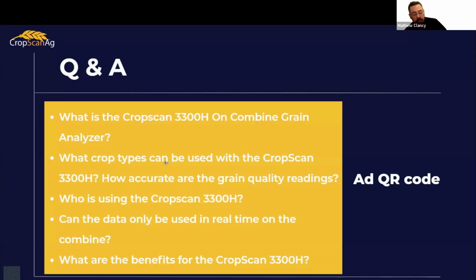When I look at the accuracy, I pour 100 samples in the machine. I've got an Infratec and I compare the two and statistically compare the differences. Statistically, I can get it within about 0.2 to 0.3 for protein, and even under 0.2 for moisture. But that's against my one machine that sits in my perfectly air-conditioned environment. We have it calibrated and managed. When you add in multiple machines at different sites and different environments, it gets pretty wild.